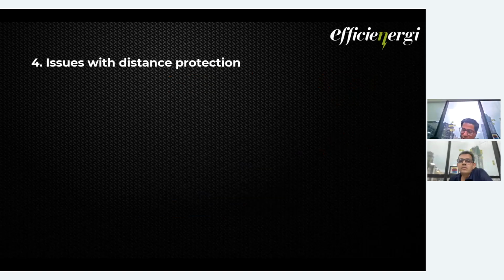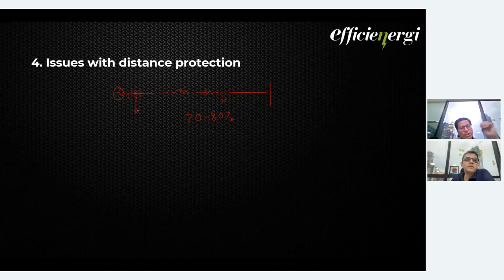Okay, then there are issues with the distance protection. So distance protection, if you know the very basics of it, is for line protection. So at generation, you have the line, right? And normally sometimes we set it at 80% of the impedance, or maybe we set it for 70 to 80%. Then what happens is, if this CT, which is installed for distance protection, gets saturated, this will not be obeyed.